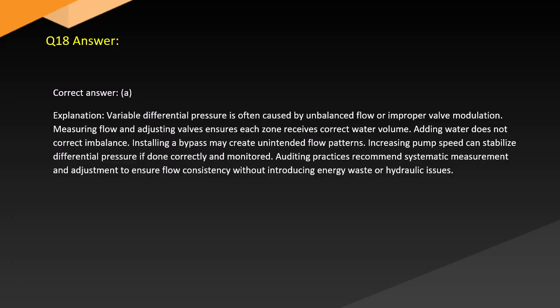Answer. Correct answer. A. Explanation. Variable differential pressure is often caused by unbalanced flow or improper valve modulation. Measuring flow and adjusting valves ensures each zone receives correct water volume. Adding water does not correct imbalance. Installing a bypass may create unintended flow patterns. Increasing pump speed can stabilize differential pressure if done correctly and monitored. Auditing practices recommend systematic measurement and adjustment to ensure flow consistency without introducing energy waste or hydraulic issues.